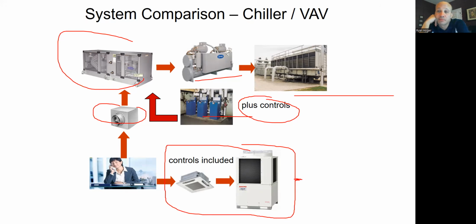If it's a high-rise building, skinny, 40 stories, not a lot of roof space, you're probably not going to do this either. I'd rather put one big cooling tower or two cooling towers on a roof than 50 of these heat pumps outside. But if it's a shorter, 2, 3, 4-story building, with more square footage wide instead of high, then it becomes an easier choice to do VRF.